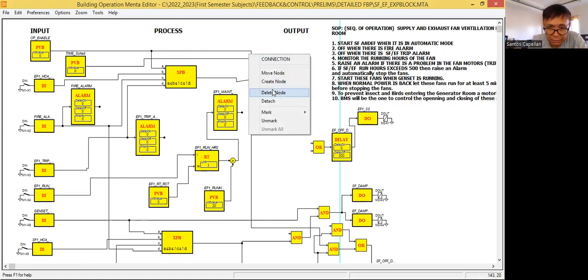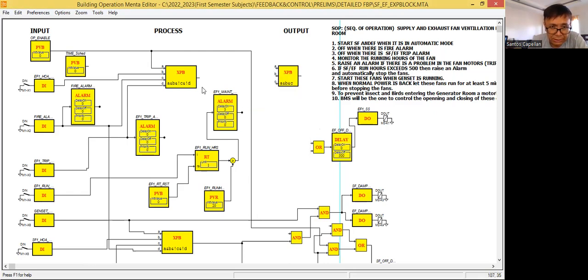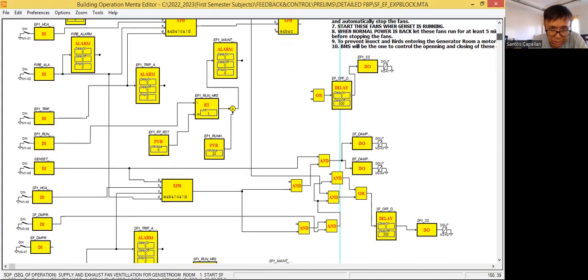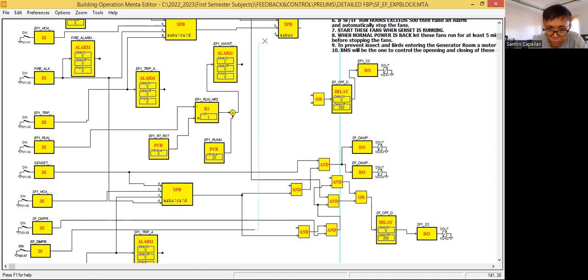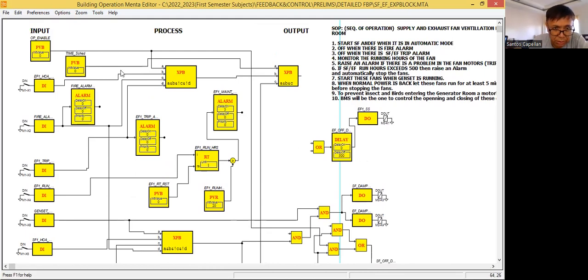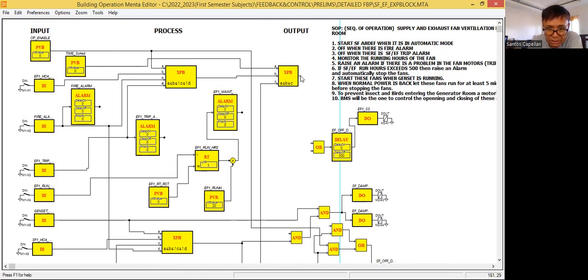Let's try to delete node. I want my logic to be clean. I need the damper EF damper status input here. So meaning: if the time schedule for maintenance is set, and everything is okay — hand operator enable EF one, power one, no fire alarm — and the damper is open, then this is one of the conditions wherein we can start our fan.